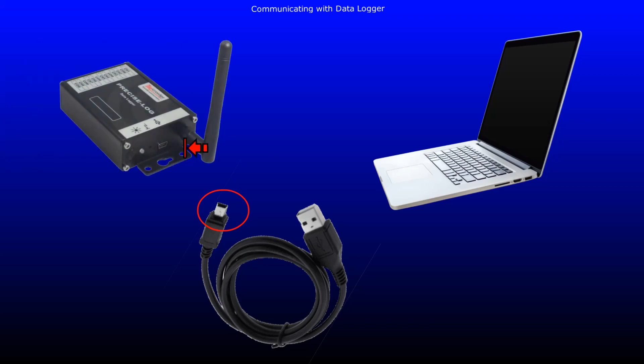The name of the icon includes the model number and the serial number of the data logger to distinguish it from other data loggers connected to this computer. Double-click this icon to communicate with the data logger. Upon success, the data logger status panel will be displayed. The status contains the general, alarm, Wi-Fi, and channel-related settings. From these settings, you will know when the data logger has started this logging session, if the logger has stopped, what sample interval was selected, how many channels are enabled, and what equation was selected for each channel, etc.